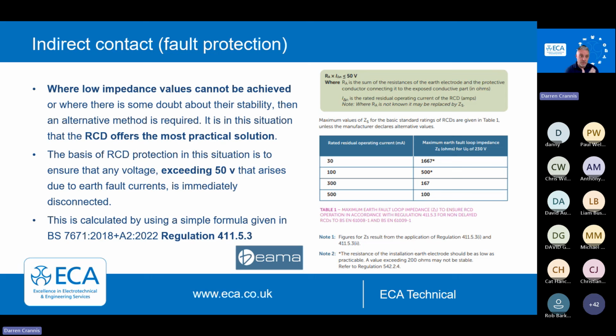We can do that with TN systems. So where low impedance values cannot be achieved, or there's some doubt in their stability, again, that's looking at TT, but can be applied to TN. There's an alternative method. And this time, an RCD is a practical solution because it allows us to go beyond those Zs values. Because the important protection by the RCD is that it's not exceeding that 50 volts. And it's that 50 volt rise in potential that can cause harm to humans and livestock. And anything over 50 volts will disconnect. And that's that 30 milliamp value.